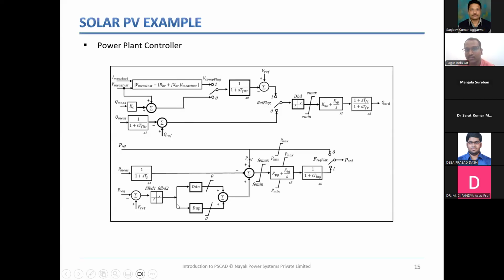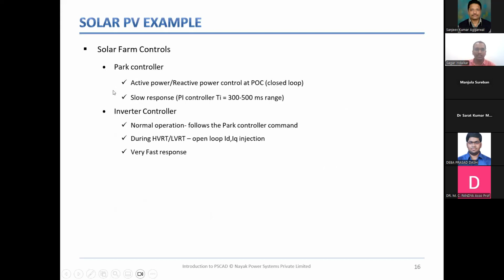Along with that, it has to perform other functions, for example, the frequency loop function, the grid support function. So you have your frequency loop here that will inject active power or reduce active power if the frequency is above or below the band specified by the grid code. A similar function it has to do for voltage controllers. There are many other controls that are typically part of a PPC. But as I said, it's a very extensive discussion, and we require another day to discuss this itself. Now, a PPC, also called a park controller, performs active and reactive power control at your regulated bus. That is POC. It's a closed loop control and it has a very slow response.